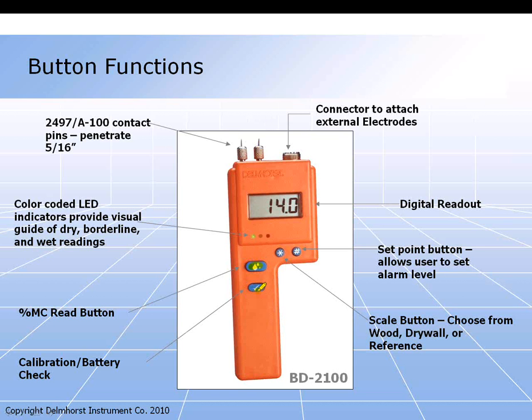The check mark is to check the calibration, and I'll go over that in just a minute. The asterisk is the scale button. That's what allows you to choose from wood, drywall, or that 0 to 100. The pound sign is the set point for the buzzer. That's what accesses the alarm value and allows you to adjust the alarm value.